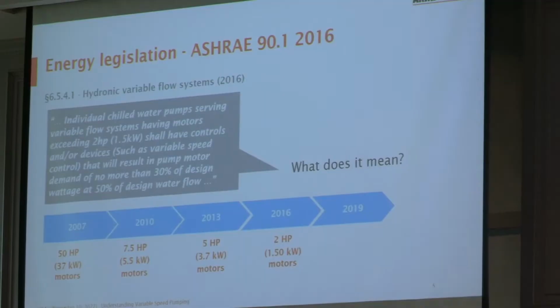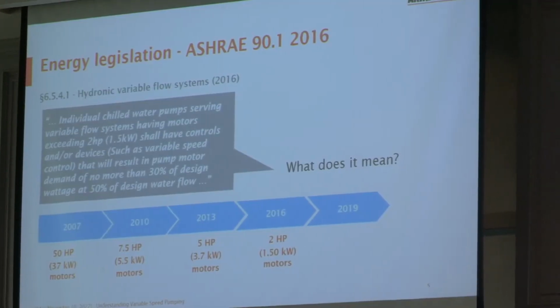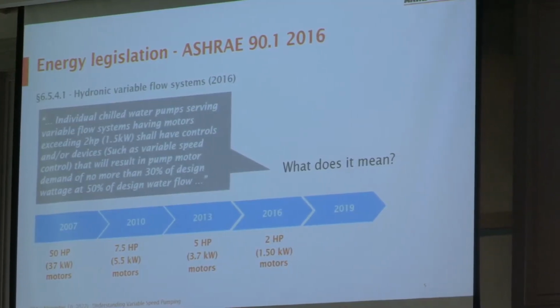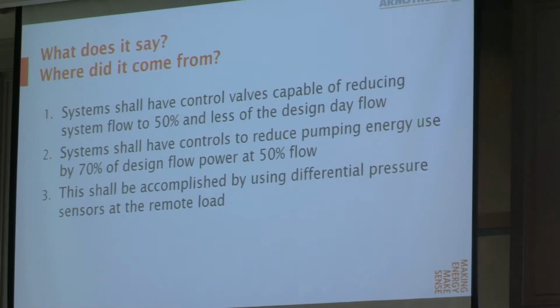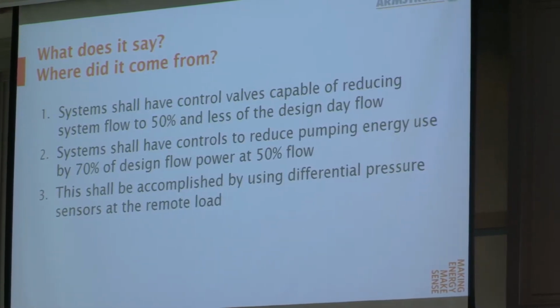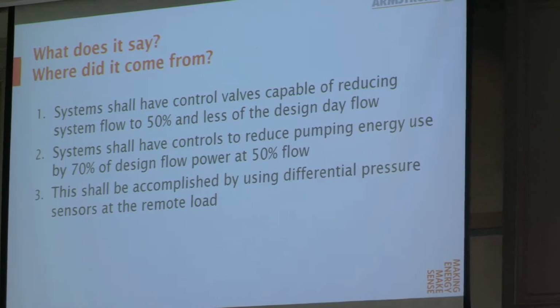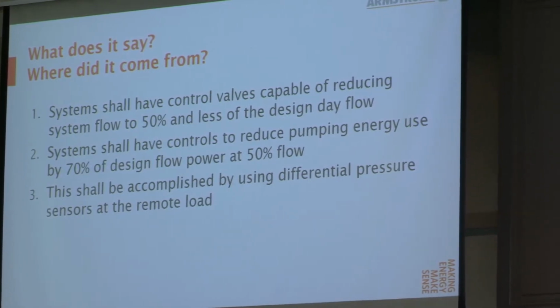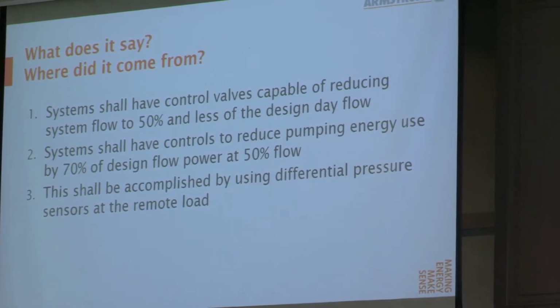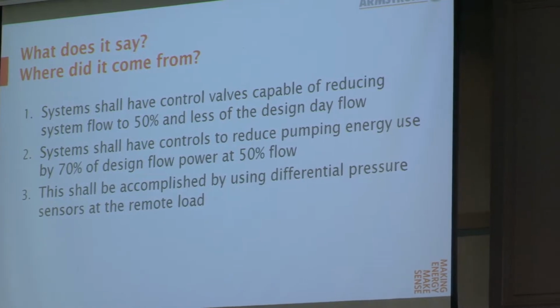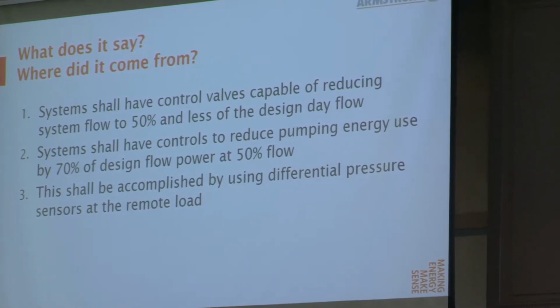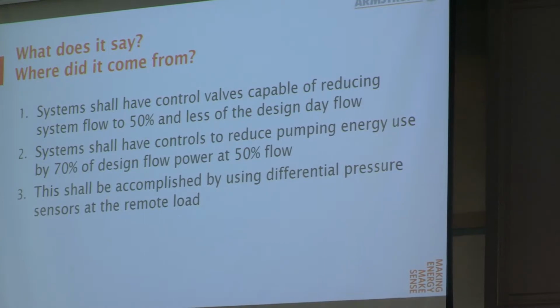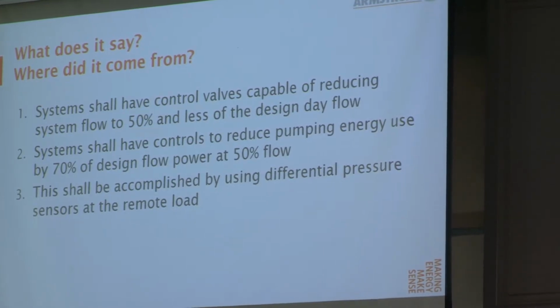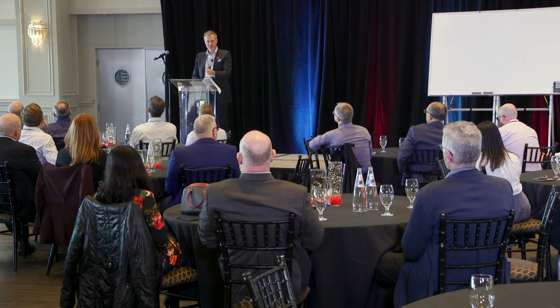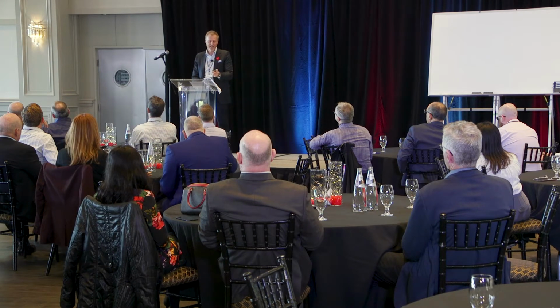So where did ASHRAE come up with this? First of all, what they are saying is that we shall have a control that when we reduce the flow of the system to 50%, we are using 30% of the energy. Two-way valves reduce the flow to that fan coil. We're going to use 30% of the energy. How did they come up with that?